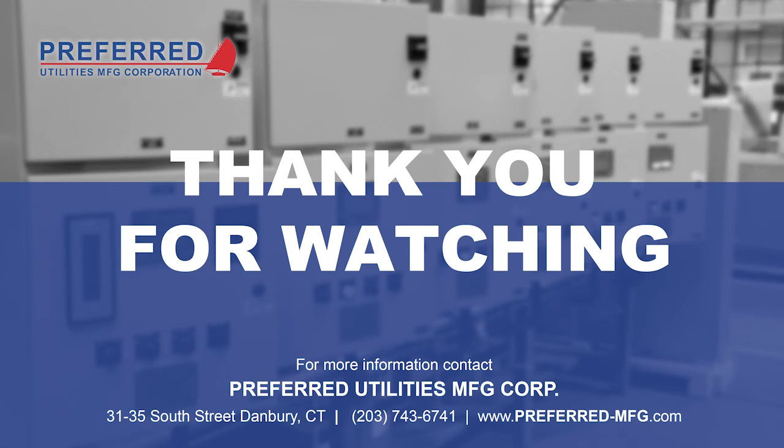And what Preferred likes to do is we like to add electric heaters to our pump sets. And then we use a routine where if the ambient air gets below set point, typically about 40 degrees, then we'll start a pump and start a heater and start circulating fuel between the pump and the main tank. And then one at a time, we will energize a return pump and pump a day tank down to the 50% pump on level, and then let the transfer pump oil back to the 80% pump off level.